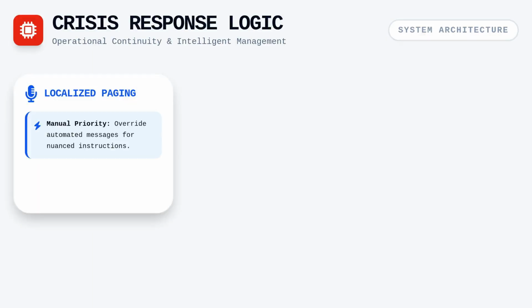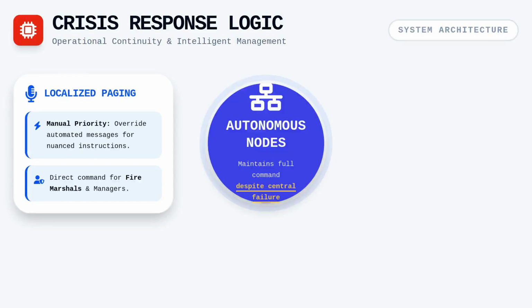Beyond physical hardware, the programming logic of the system defines how the facility responds during a crisis. We are tasked with setting priorities for localized microphone paging, allowing fire marshals or facility managers to override automated digitized messages when specific, nuanced instructions are needed. These control units must be autonomous, maintaining the ability to command the building even if the connection to the main fire alarm control panel is interrupted. This decentralization of control provides a buffer against system-wide failures while ensuring that vital instructions can be delivered locally.